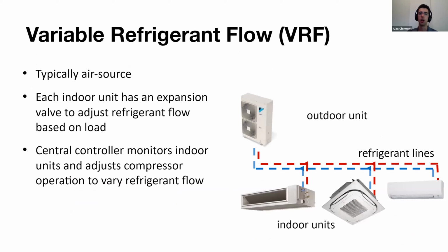Next, we'll get into another type of air source heat pump. This is probably Eric's and my favorite topic, but now we're looking at one of the most common commercial air source heat pumps, which is VRF, or variable refrigerant flow. With these, each indoor unit has an expansion valve which can adjust how much refrigerant it wants based on the load, and the outdoor unit will in turn modulate the compressor to adjust for the amount of refrigerant needed in real time based on what the indoor unit is asking for, hence the name VRF.